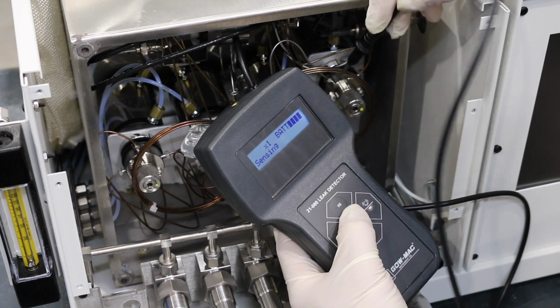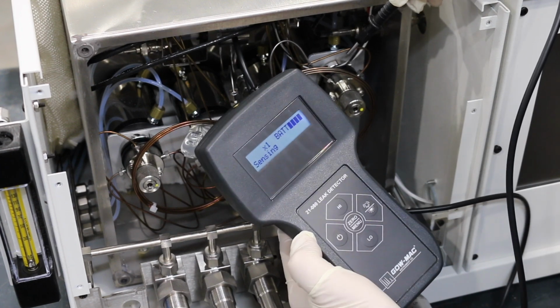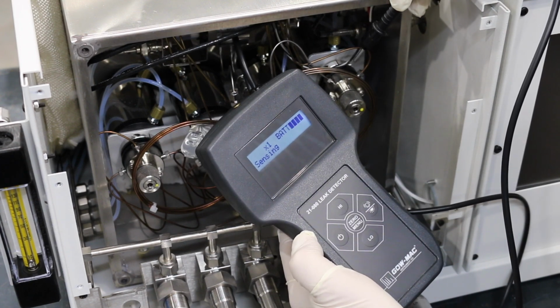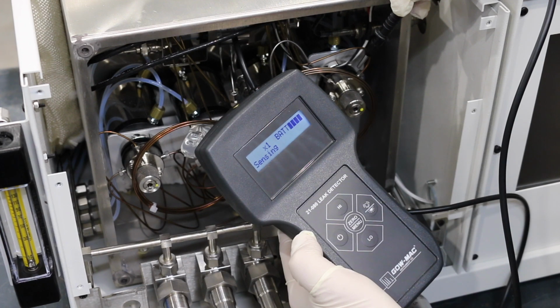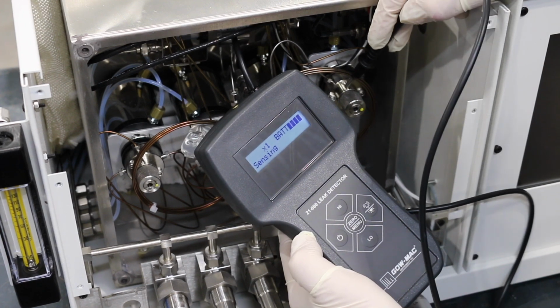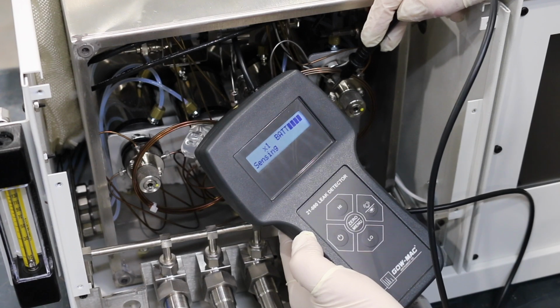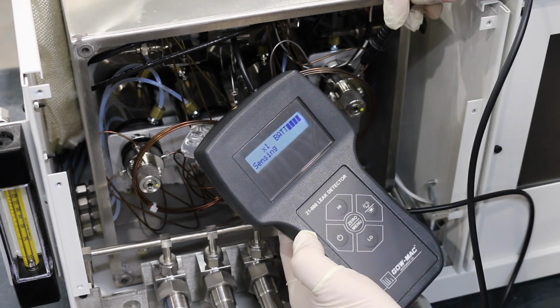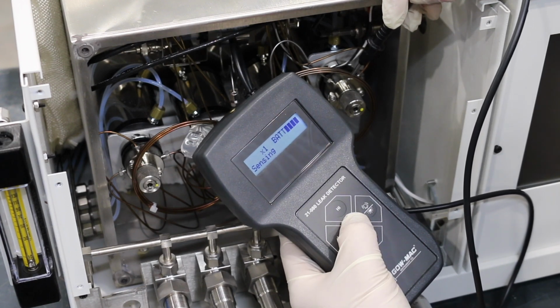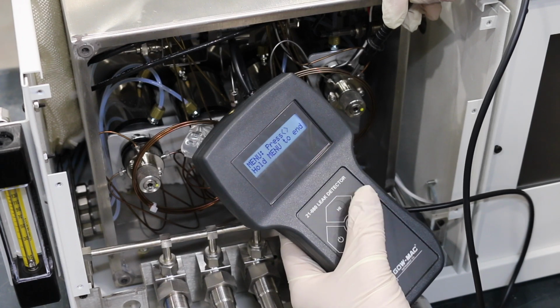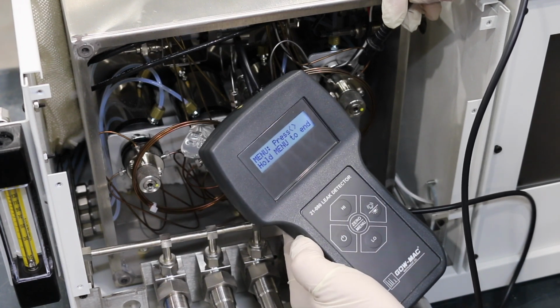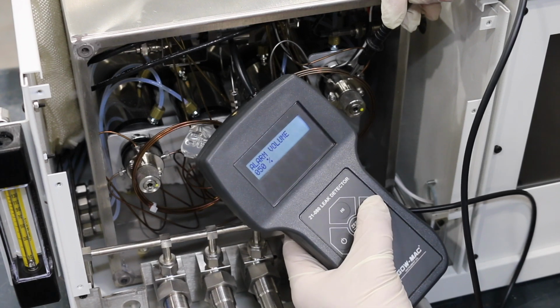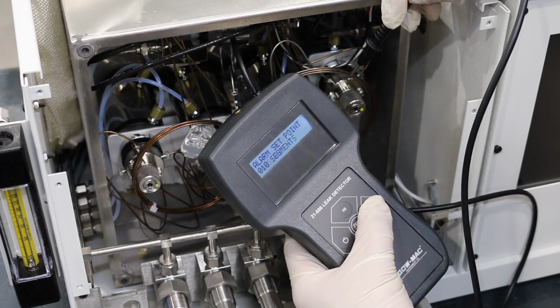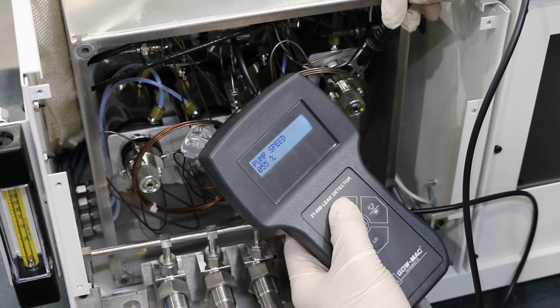The menu on the 21080 features an array of configurable operating parameters to optimize the instrument for your specific application. Leak detection is suspended while settings are being changed. Long press the Menu Zero button to open the menu screen. To set a certain parameter, you must scroll through the other options. You can scroll using the power and the alarm backlight buttons. When a certain parameter is on the screen, use the high-low buttons to change the value.